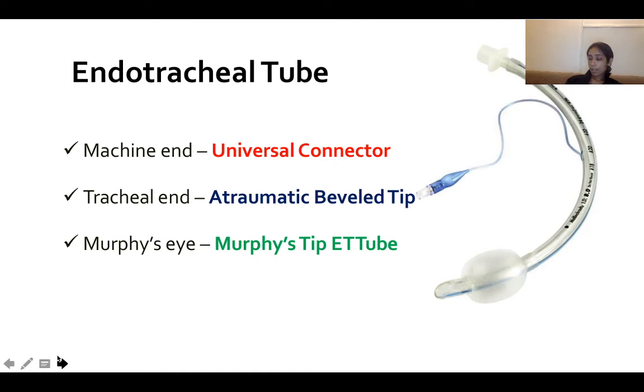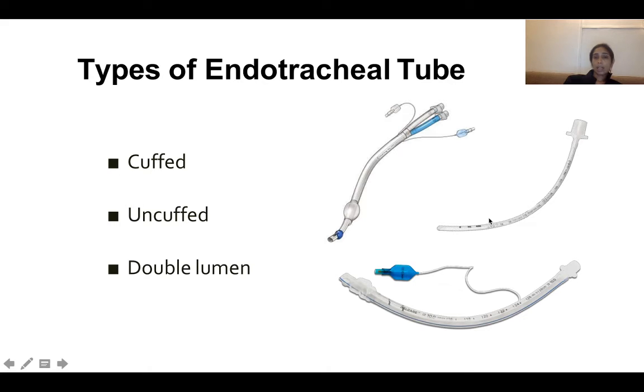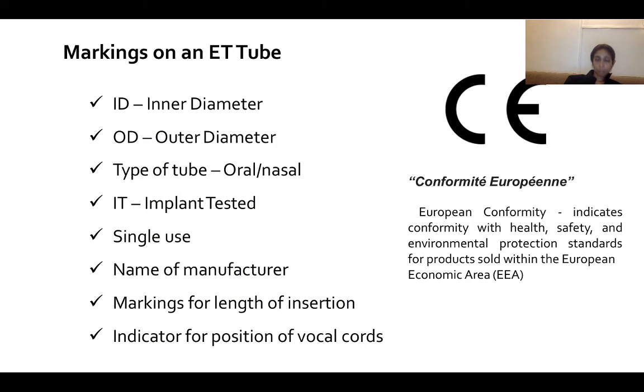Machine end is the universal connector, and the tracheal end is an atraumatic bevel tip. There's a Murphy's eye just in case the bevel gets blocked, so secretions can drain through the Murphy's eye. They are cuffed, uncuffed, and double lumen. These are the various markings on the endotracheal tube: the internal diameter, outer diameter, the type of tube, oral, nasal, implant tested, single use, and markings for insertion. All these are the various markings present on these endotracheal tubes.